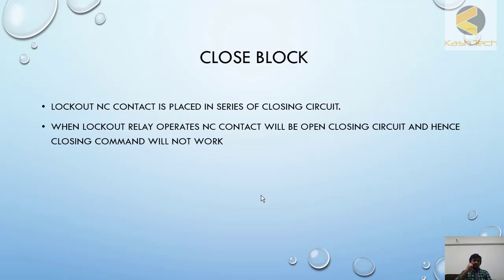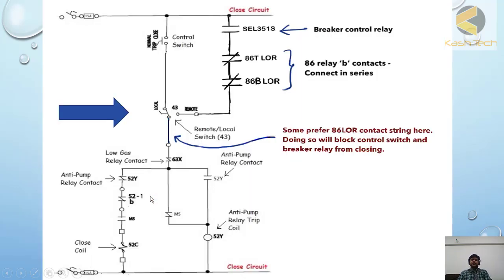You can see here the two lockouts are in series. When lockout will operate, both circuits will become open. If there are five lockouts, five lockout contacts you have to put in series. If any one of the lockout operated, the breaker cannot be closed.